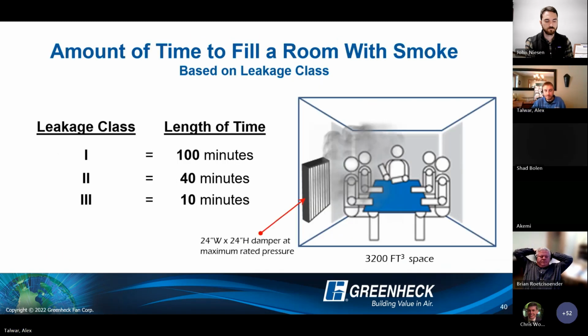whether it's external or internal. So let's put that leakage class into more realistic terminology, in terms of stick figures sitting in a little cartoon room here. If that is a class 1 rated smoke damper protecting those stick figures, they will have 100 minutes of time to get to safety. If it's a class 2 rated product, it's cut a little bit more than in half, but they should still have plenty of time to get to safety, 40 minutes, and then class 3, maybe 10 minutes to get to safety.